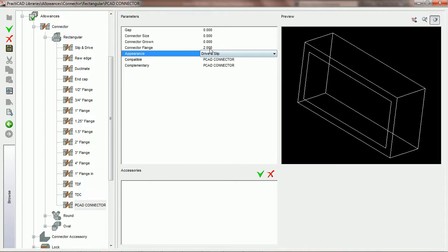When you say 2-inch connector flange, that means that this connection will be 2 inches on the inside face of the fitting. It will not take up any length of the fitting. However, if we go to snap a grill to the 2-inch connector flange, if the duct was 36 by 18, the grill's neck would now be 32 by 14 because we'd lose 2 inches on each side, so 4 inches.